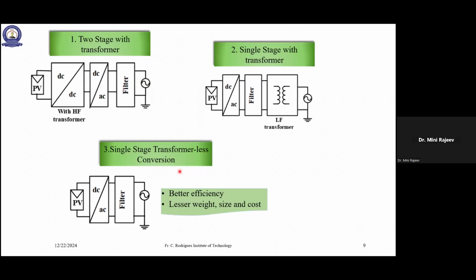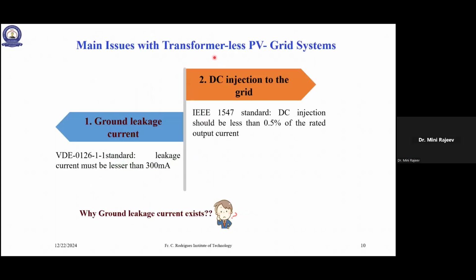But what is the cost we are paying for? Nothing comes for free. So the main issues of transformerless PV grid systems are, one is ground leakage current. According to this German standard, leakage current must be lesser than 300 milliamperes. And DC injection into the grid.